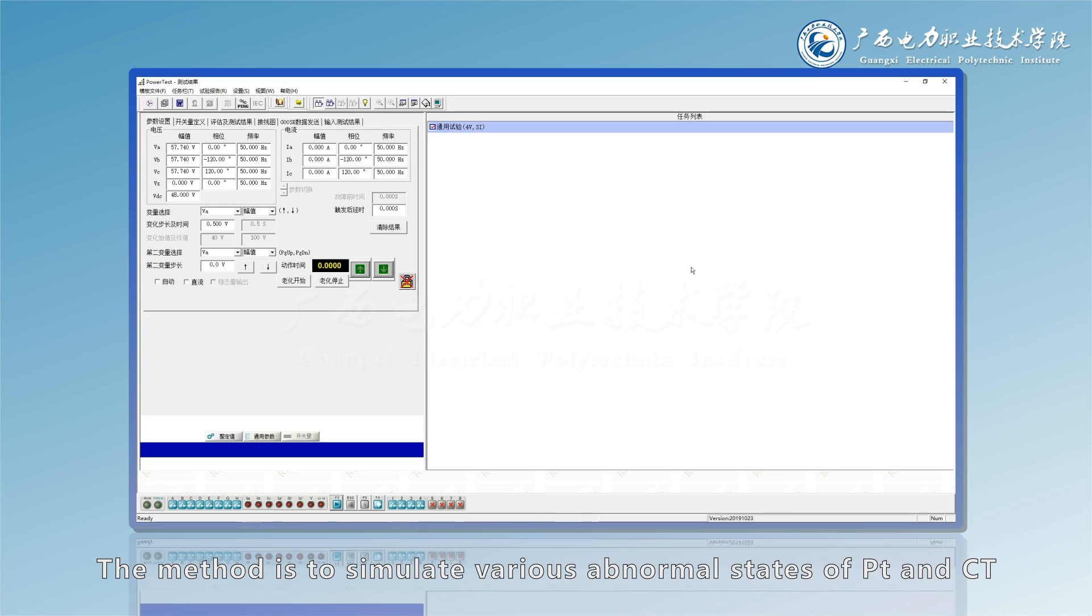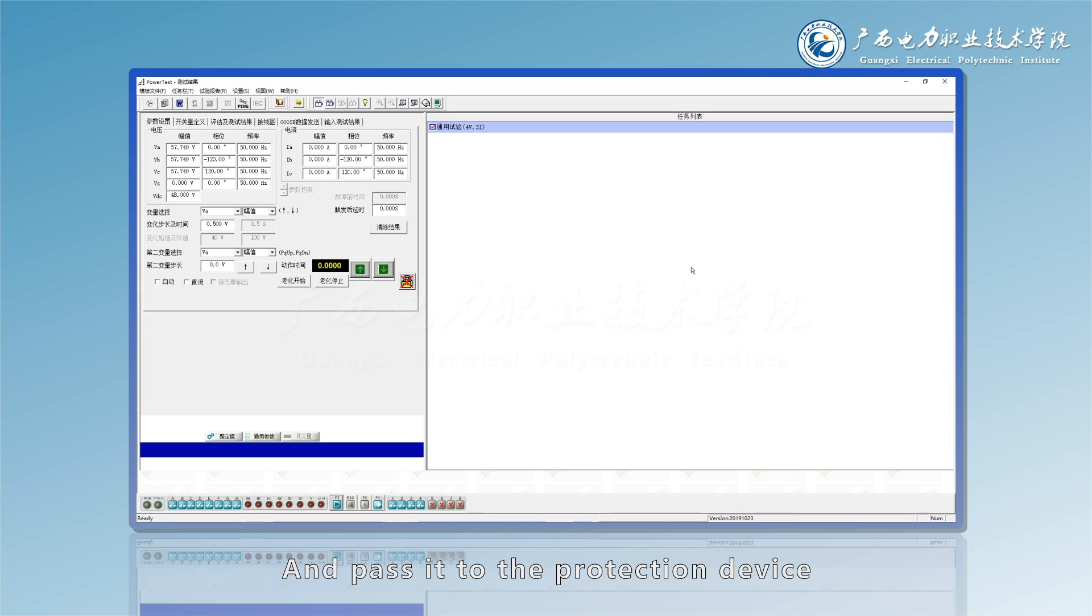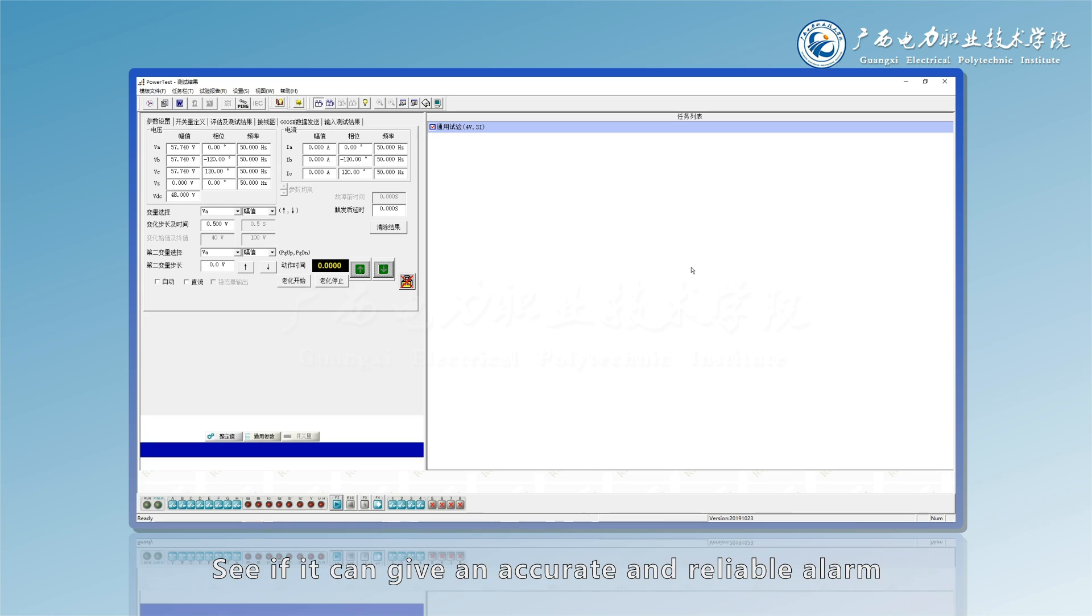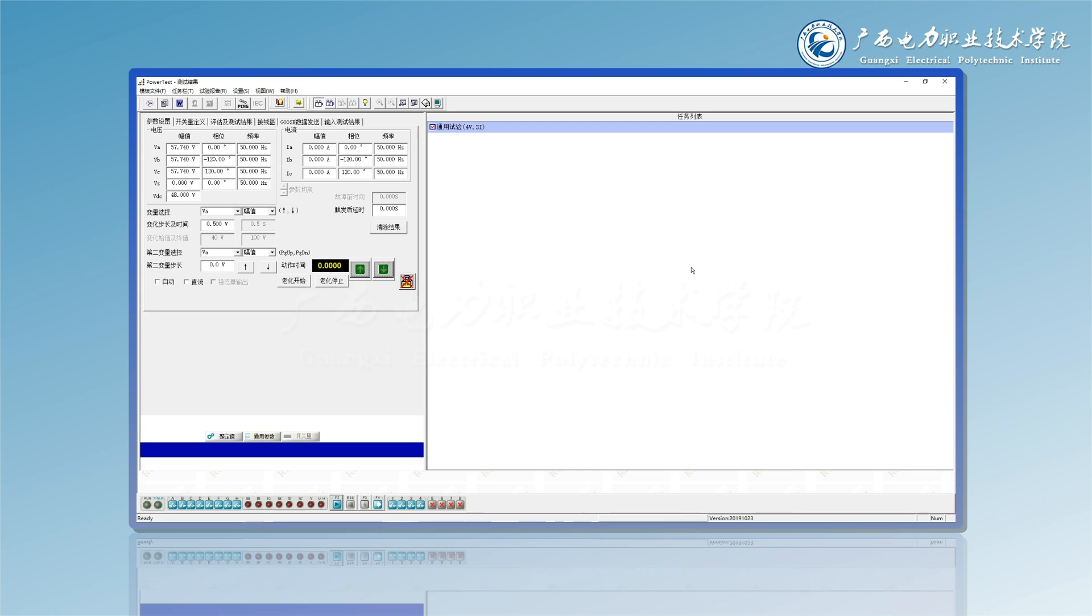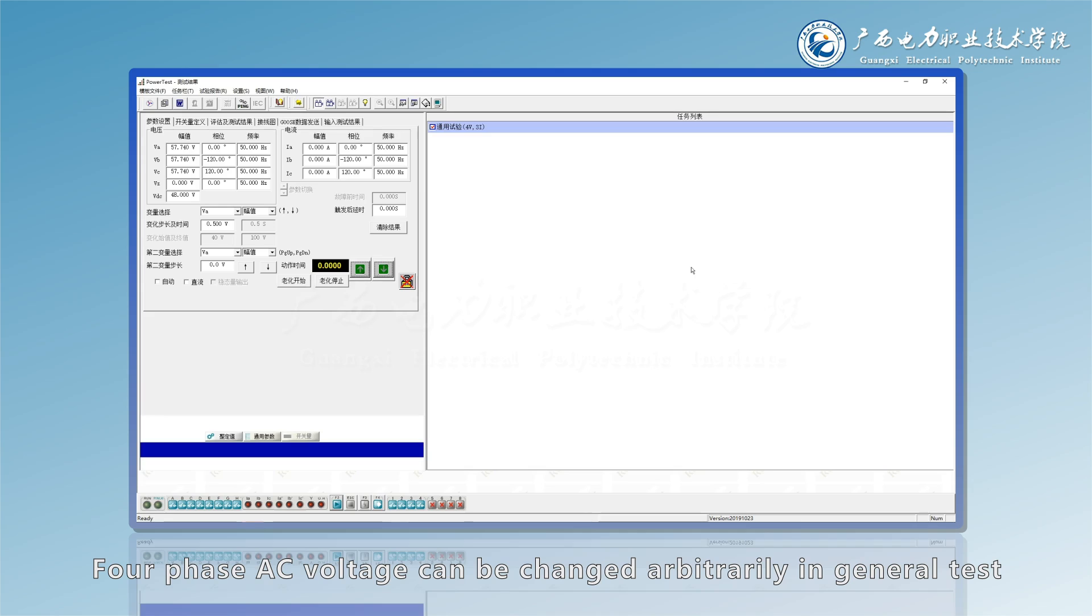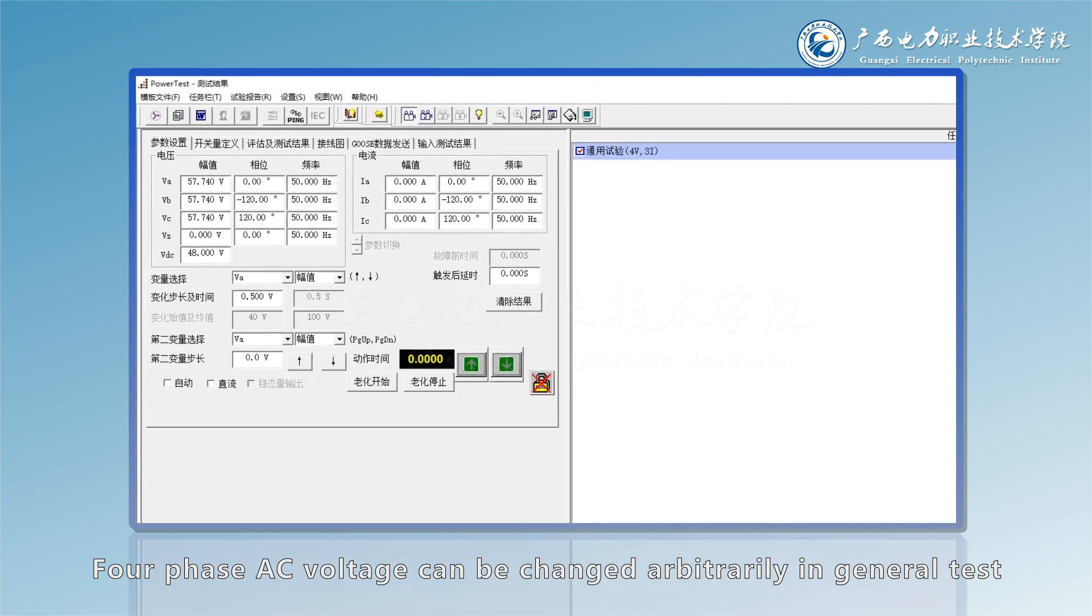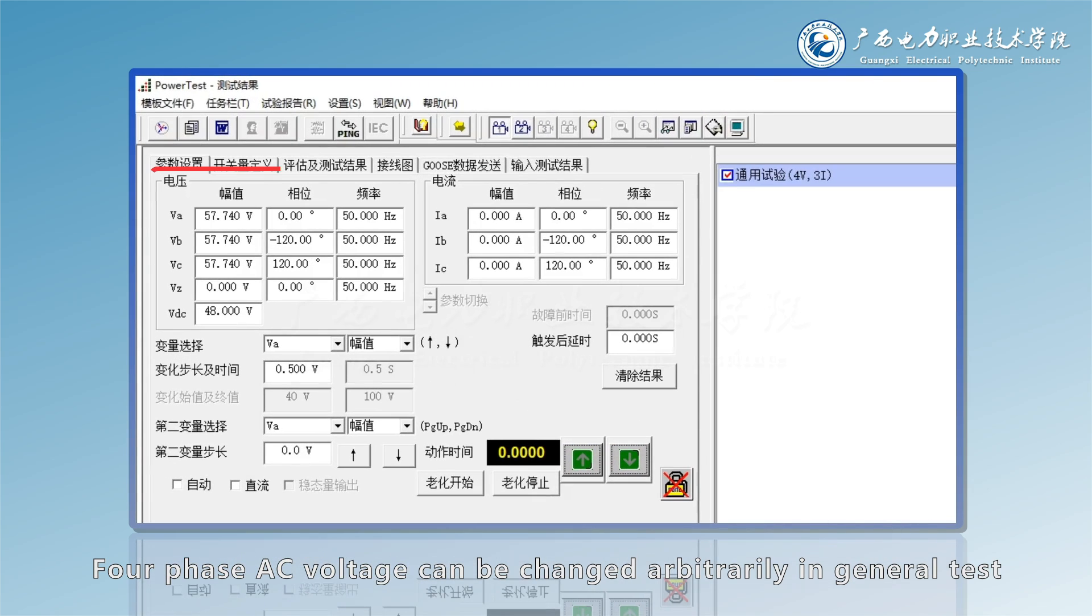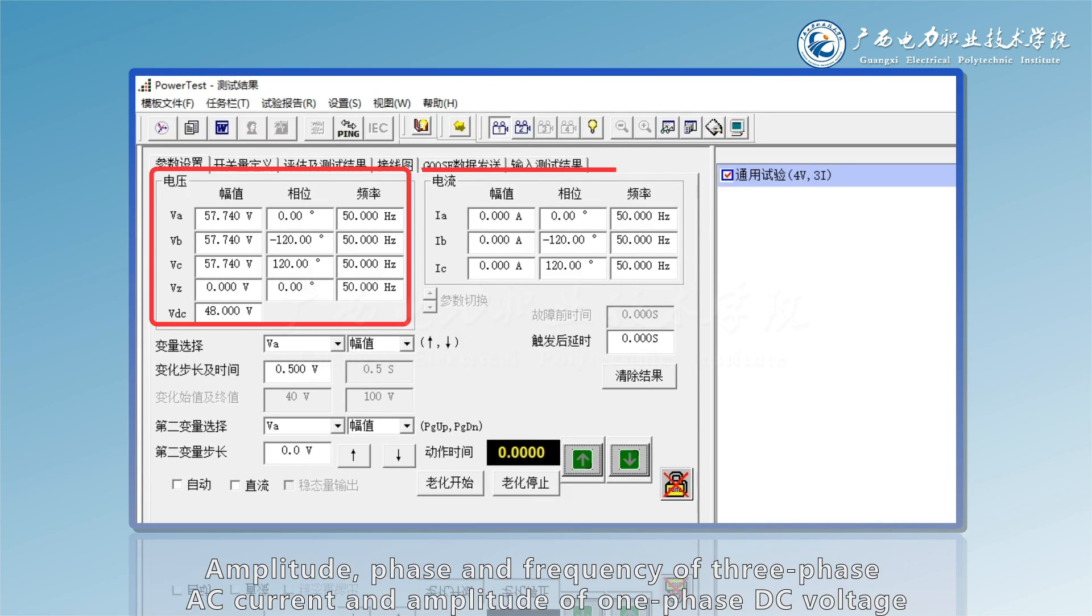The method is to simulate various abnormal states of PT and CT and pass it to the protection device. See if it can give an accurate and reliable alarm or remove the fault. In general test, 4 phase AC voltage amplitude, phase and frequency of 3 phase AC current and amplitude of 1 phase DC voltage can be changed arbitrarily.